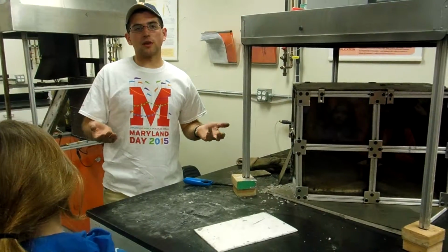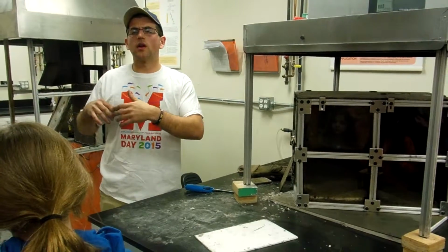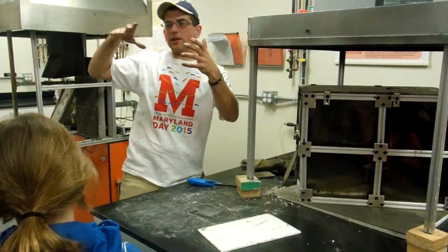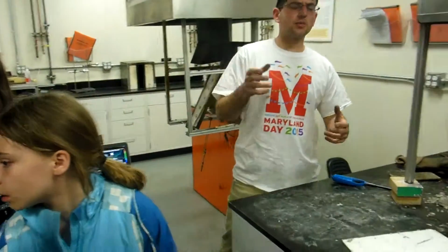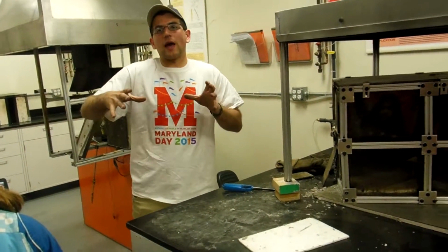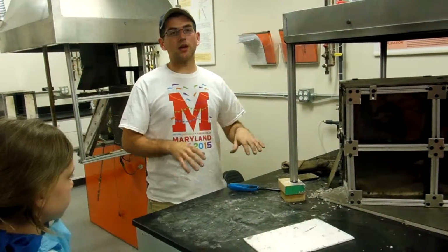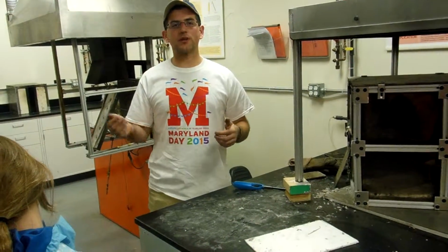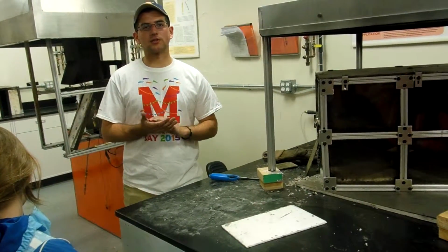So it's definitely something that we have to look at, and that's why, I'm pretty sure in Europe, Dr. Sunwood, in Europe, they use a lot more compartmentalization, right, with their buildings. Right. They don't use sprinklers as much. Less wood in their construction. Yeah, so in Europe they use less wood, they compartmentalize more, but they don't use sprinklers as much because you have fewer combustibles, and you have that compartmentalization to stop the fire from spreading. Here, we don't compartmentalize as much, we use more flammable materials, and because of that, we tend to use sprinklers a lot more. So, we can think about all these things when we're designing stuff.